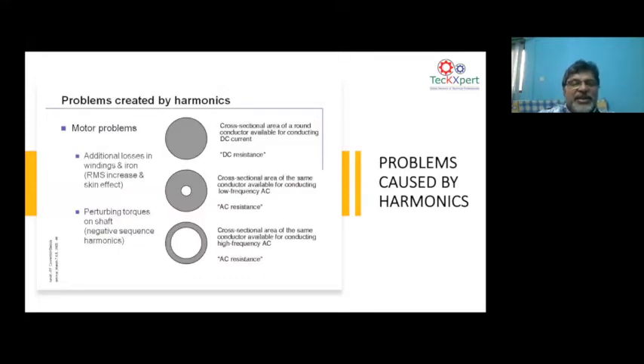As I said before, the skin effect problem: the higher the harmonics, the higher the resistance. Because if you take a cable and inject a 50 cycle current, you can see in the middle picture it has an AC resistance which is increased, and even the area of current flow is reduced. You take a harmonic current, you will see the area of current flow reduces to a very small peripheral area. That means your effective resistance is going to increase, because resistance is rho into L by A, and if the area comes down, your R goes up. That means higher the harmonics, higher the resistance, higher the resistance, higher the I squared R losses.